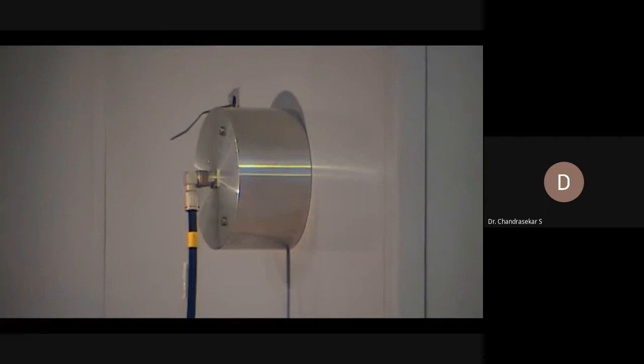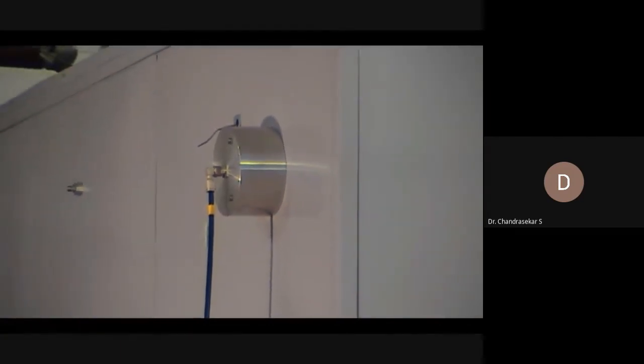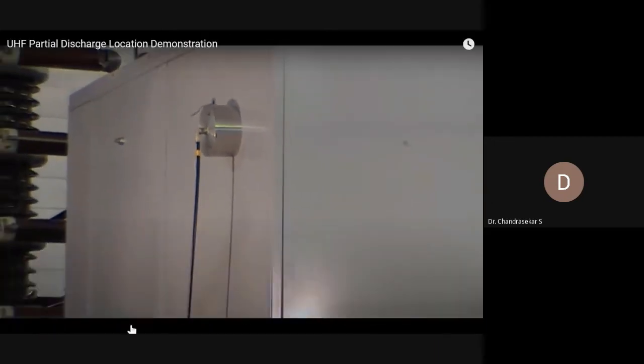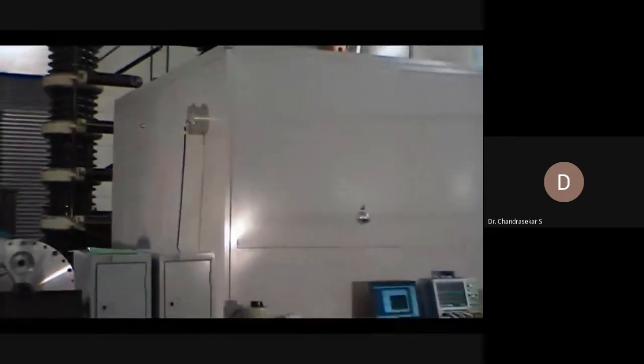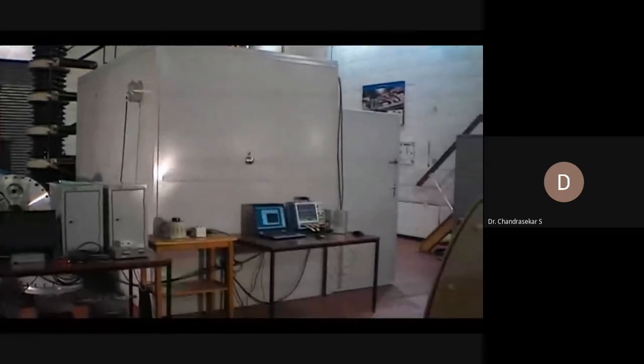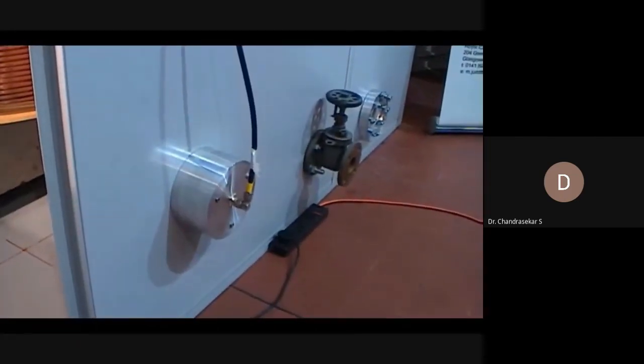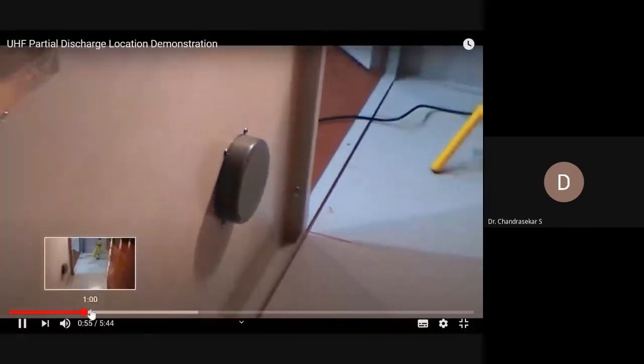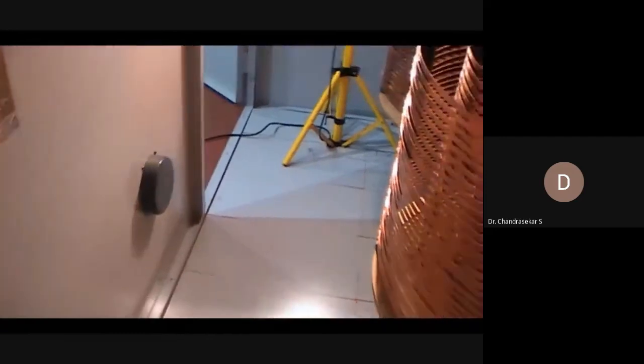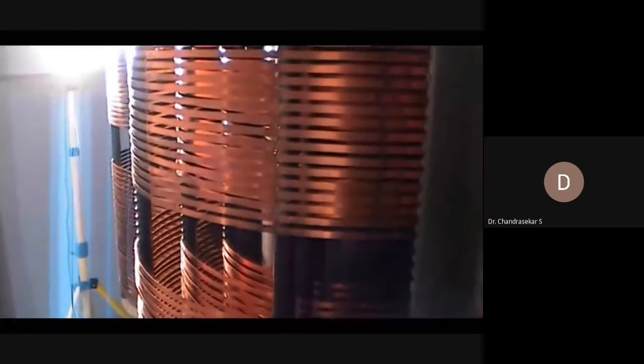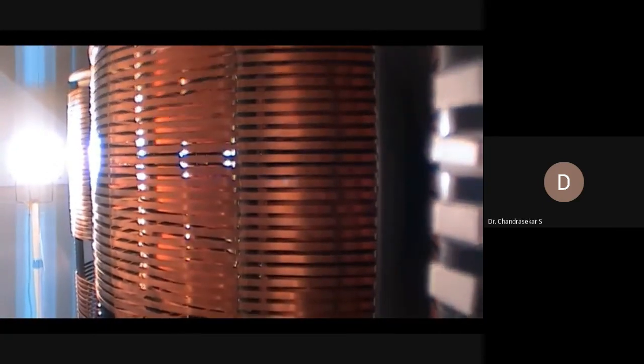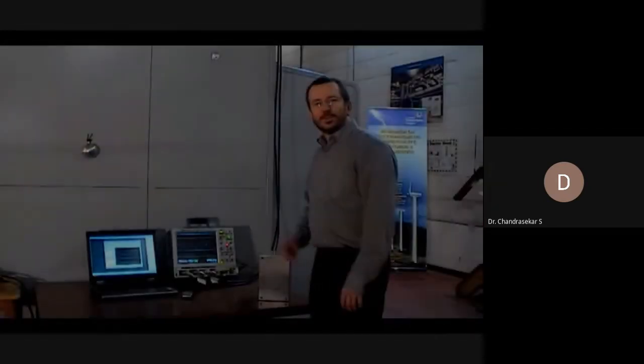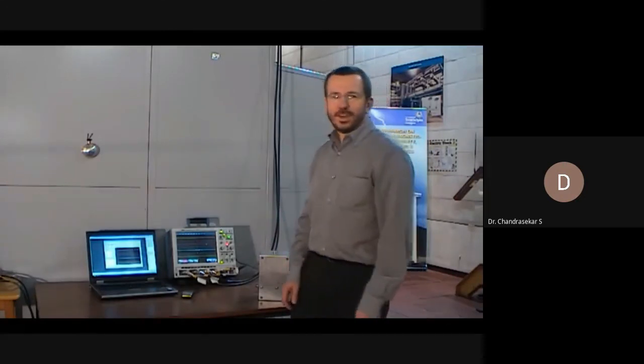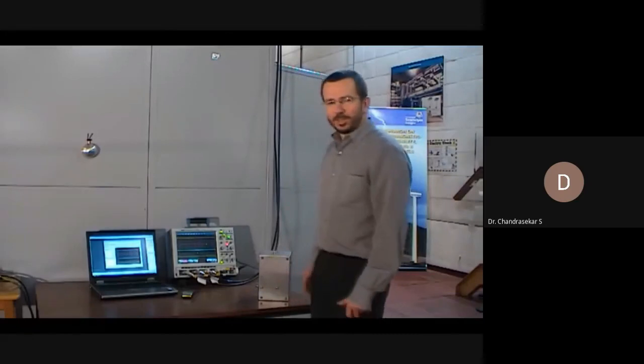So this is the UHF sensor, which is installed on the metallic tank. Inside you can see the windings, the high voltage windings. Right, the oscilloscope is now ready and connected to the 4 UHF sensors, and the PC is ready to log the data from the partial discharge once it becomes active.